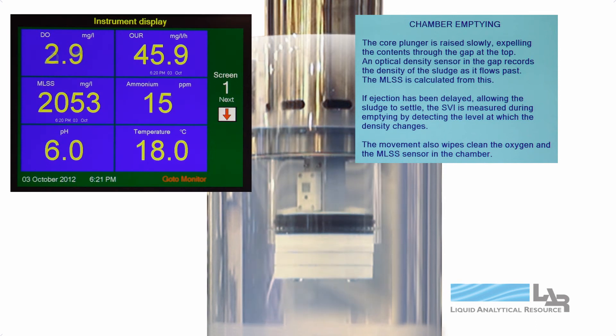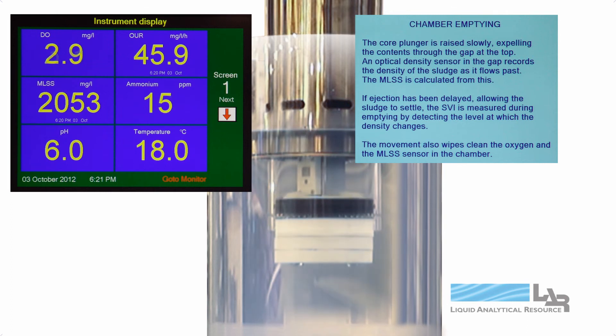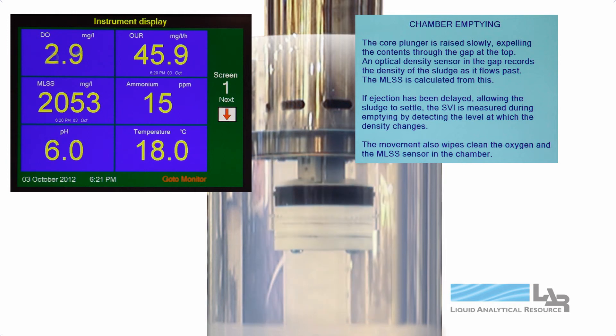The core is raised slowly, expelling the contents through the vents in the top. An optical density sensor in the vents records the density of the sludge as it flows past. This provides the necessary data to calculate the mixed liquor suspended solids.